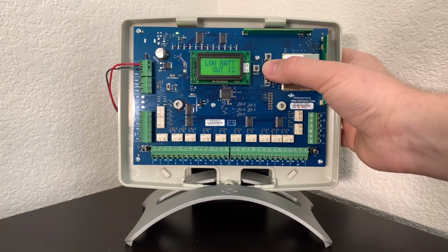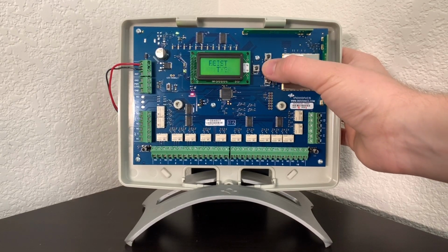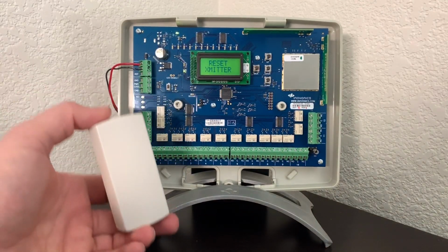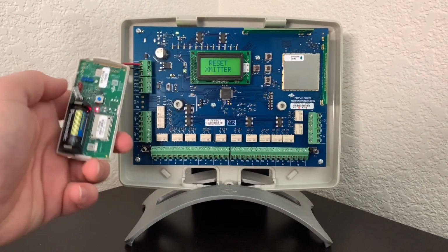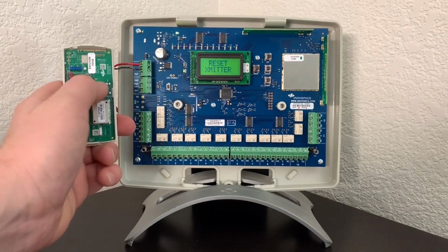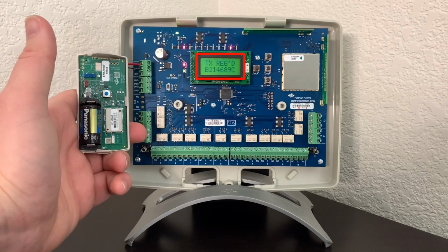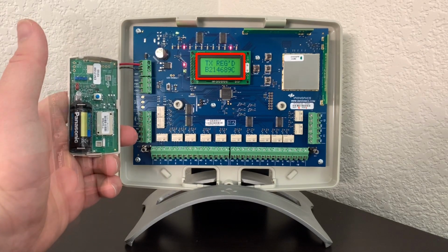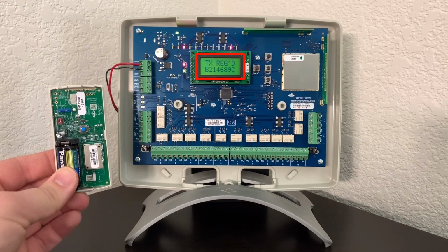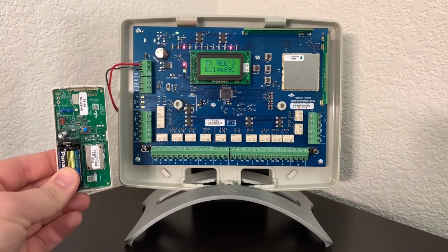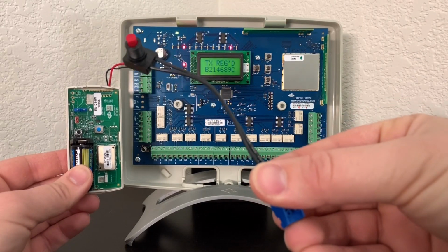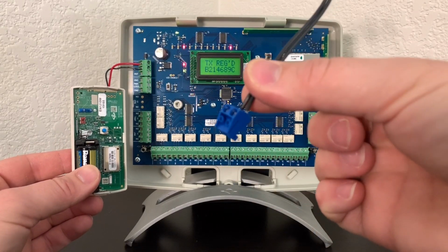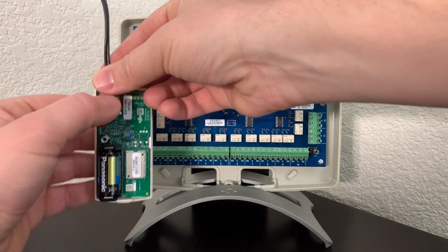We'll go through our trouble conditions again, and then entering in our text for the transmitter and registering. This time, the reset button is on the inside of the EN1210W. When we press the reset button, we should see the indication come through that it registered. We can now normalize our transmitter by wiring up any external contacts, closing up the cover, and putting the magnet by the reed switch. I'm using a simple single button wired into the input terminal.